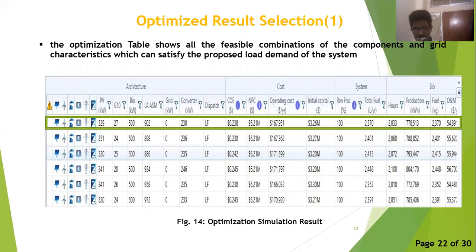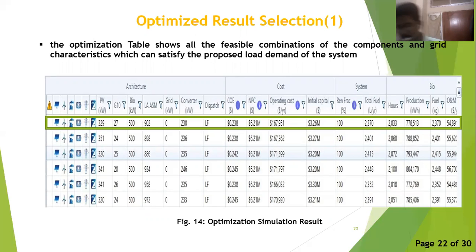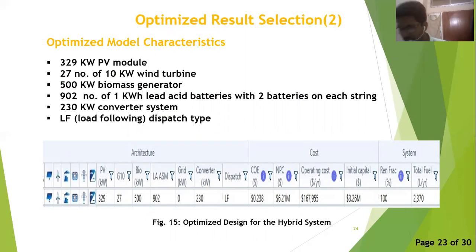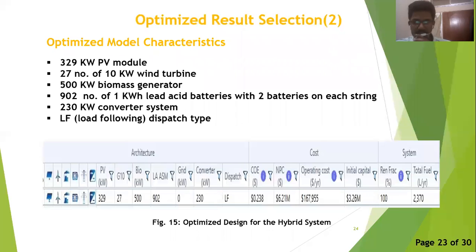Now that we know the resources and component characteristics used in the hybrid system, we can apply the simulation process using HOMER. HOMER evaluates all possible combinations of components to satisfy the load demand. All possible solutions are shown in the optimization table in figure 14, categorized based on the lowest net present cost. The chosen optimized result contains 329 kW PV array, 27 units of 10 kW wind turbines, a 500 kW biogas generator, 902 units of 1 kWh lead-acid batteries with two batteries per string, a 230 kW converter system, and a load-following dispatch type.